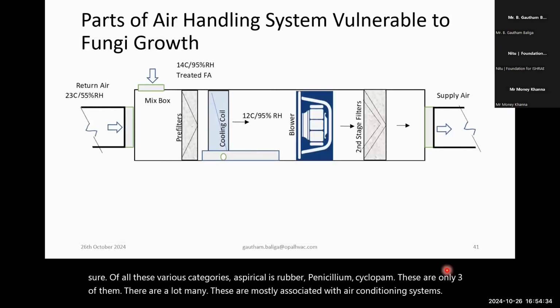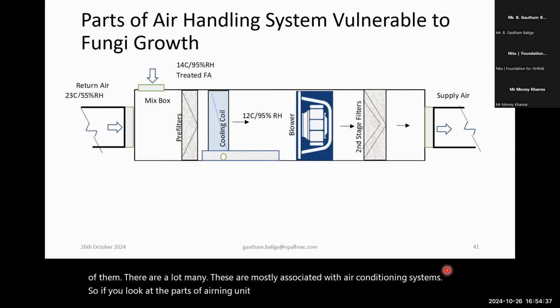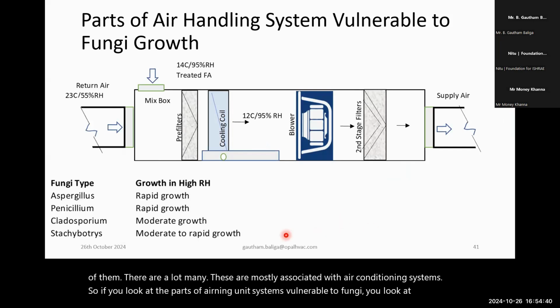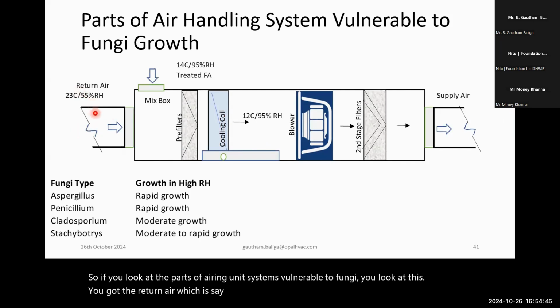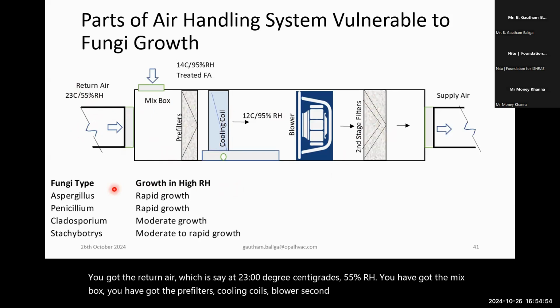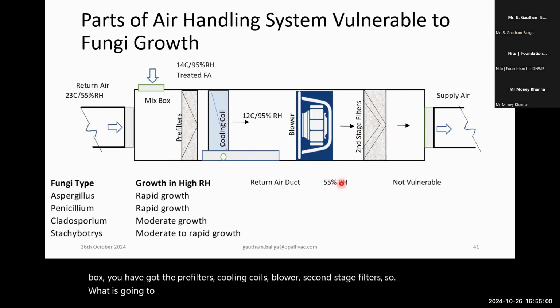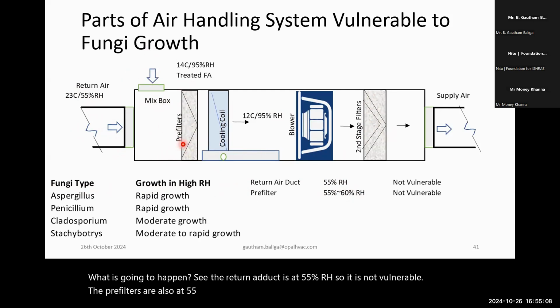So if you look at the parts of air handling unit systems vulnerable to fungi, you look at this. You've got the return air, which is say at 23 degrees centigrade, 55% RH. You've got the mixed box. You've got the pre-filters, cooling coils, blower, second stage filters. So what's going to happen? See, the return air duct is at 55% RH, so it's not vulnerable. The pre-filters are also at 55 to 60% RH, having mixed with the treated fresh air or fresh air. It's going to be in this range, not vulnerable.